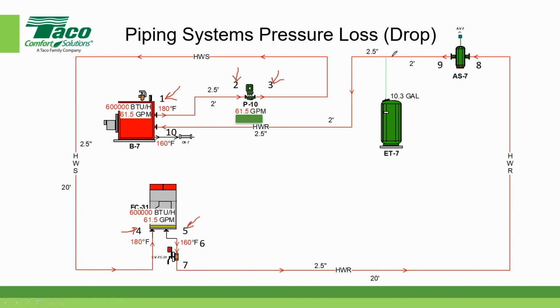I could have put in a point here where the connection is for the expansion tank, but the pressure drop across a T for an expansion tank is generally negligible, so I generally don't count that. And then the last point is all the way back to the boiler, number 10.